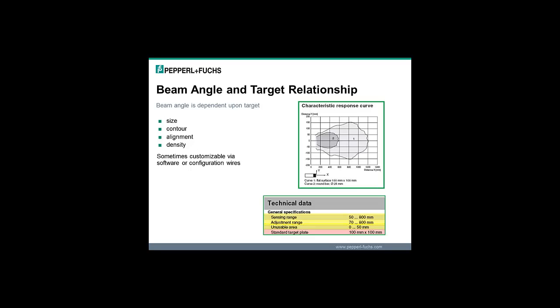So you can see, if it's a flat plate, you can detect it much further away and in a much wider area than if it's a rounded target, which is much less reflective, and also it's smaller. So the beam angle is dependent upon the target size, the contour, whether it's flat and much more reflective, or round where some of the sound disperses when it hits and doesn't come straight back to the sensor. It's dependent upon the alignment, how perpendicular it is to the target. And also the density. If it's something soft like a felt or a foam or something, it's going to be much more difficult to detect than if it's a nice, hard, acoustically reflective part.